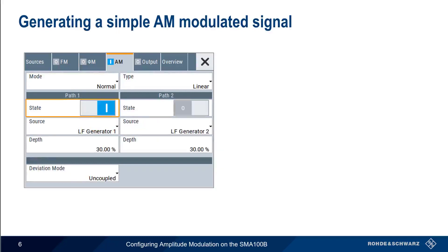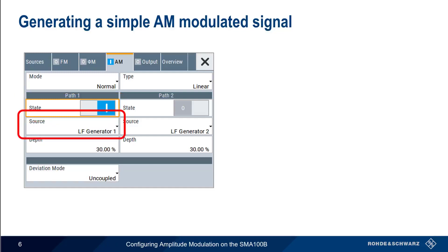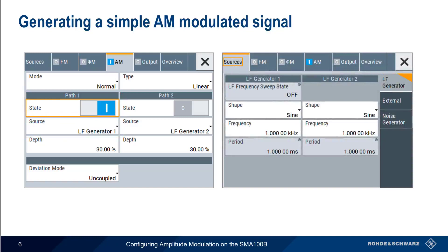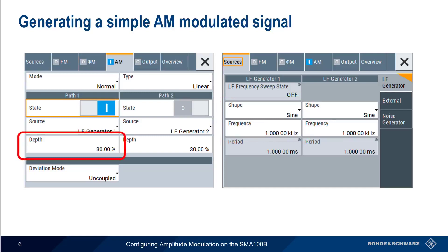If we want to generate a simple AM modulated signal, we can do this by enabling AM modulation and selecting LF generator 1 as our source. In this example, we'll leave the default LF generator setting of a 1 kHz sine wave. If needed, AM modulation depth can be configured as well. All that's left now is to turn on RF, and the SMA will be producing a basic AM modulated signal.